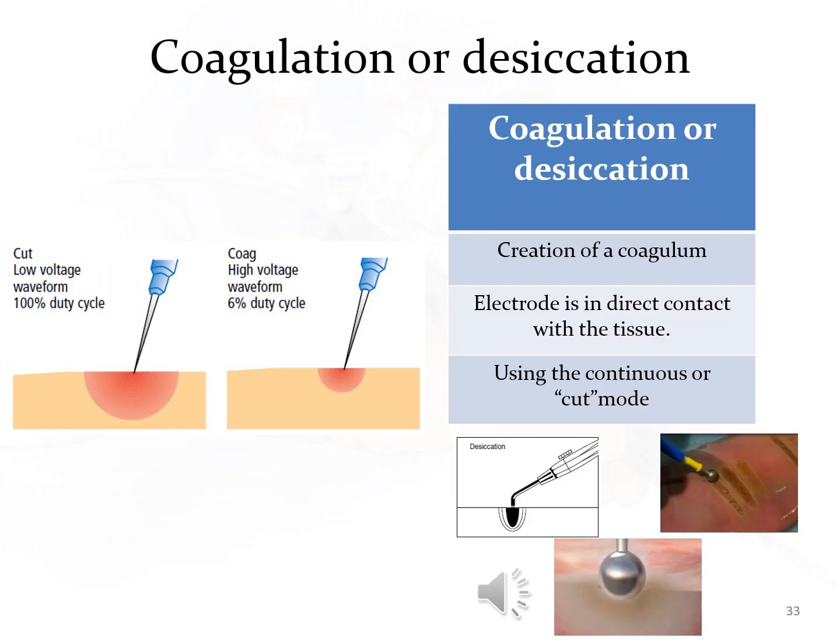Electrosurgical desiccation occurs when the electrode is in direct contact with the tissue. Desiccation is achieved most efficiently with the cutting current. By touching the tissue with the electrode, the current concentration is reduced, less heat is generated, and no cutting action occurs. The cells dry out and form a coagulum rather than vaporize and explode.